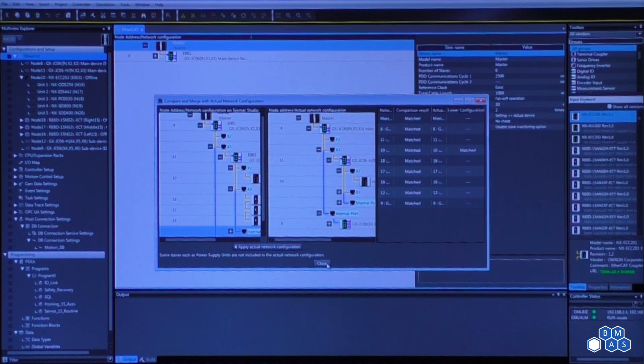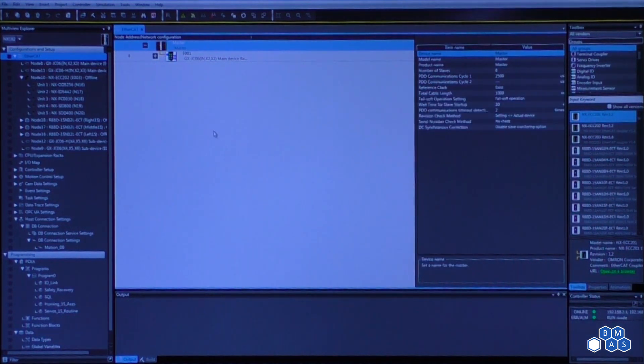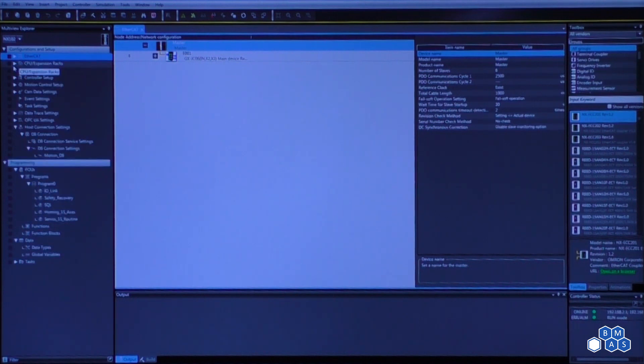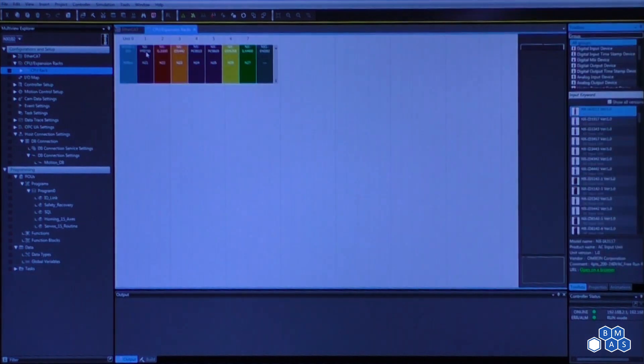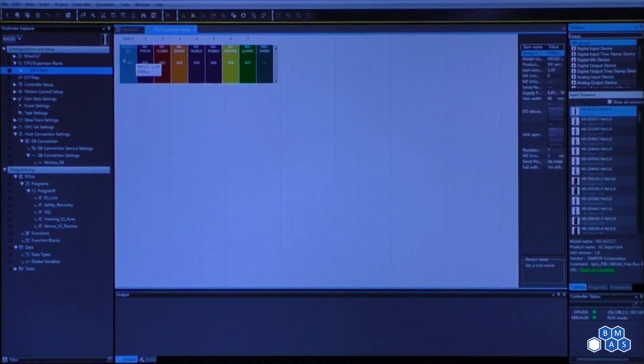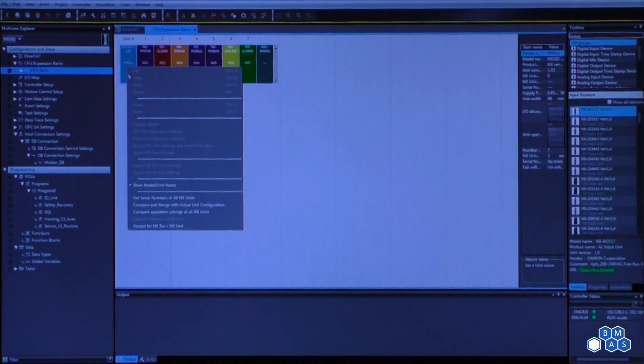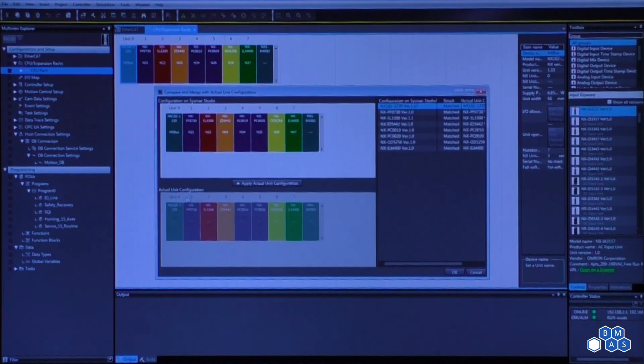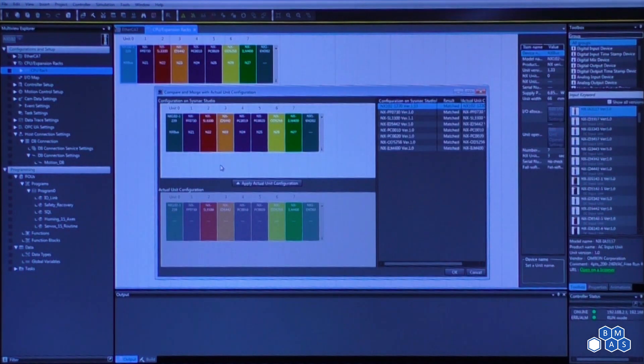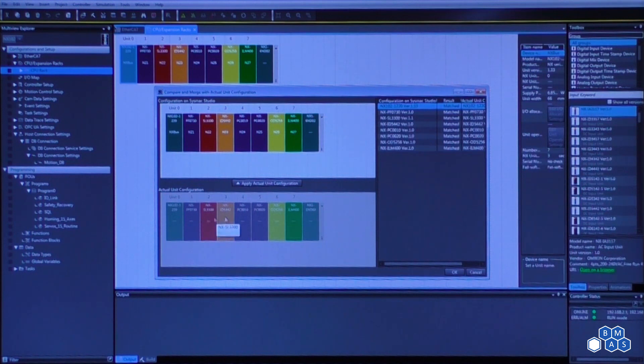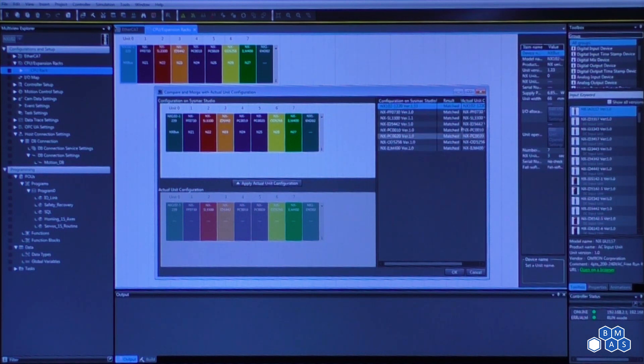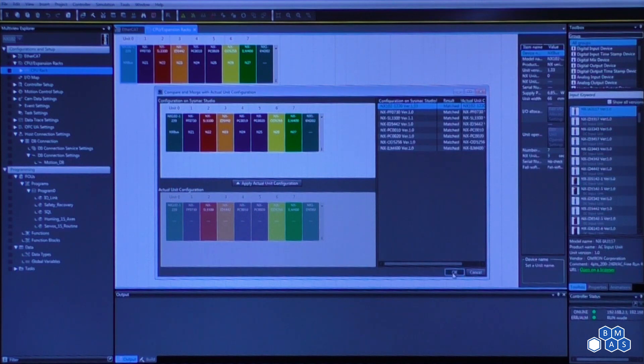Once we apply that, we can close this window. As we mentioned, we're working from the top down, we would now go to the CPU expansion racks. Again, we would do the same concept of what we just did, right click on the processor, compare and merge with the actual configuration. This is what is actually there, this is what's in the software configuration right now. If we wanted to apply it, we would just click on the button. Since everything matches, we can just hit OK.